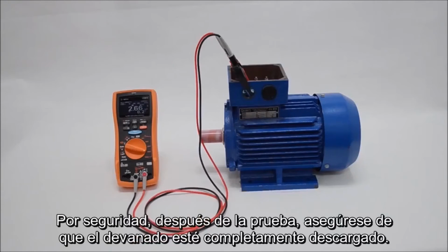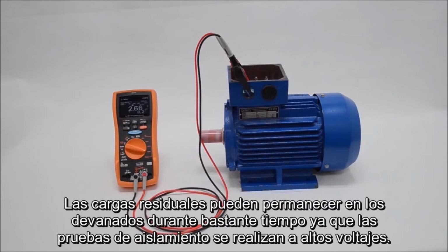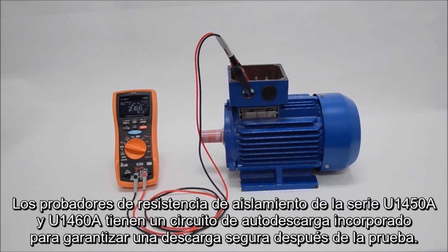For safety, after the test, make sure the winding is fully discharged. Residual charges may stay in the winding for quite some time, as the insulation testing is done at high voltages. The U1450A and U1460A series insulation resistance testers have built-in self-discharge circuits to ensure a safe discharge after the test.